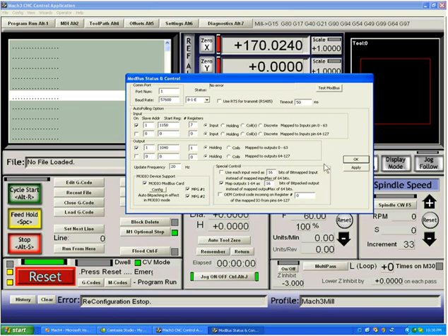Here under Special Control, we have some controls that allow you to configure a bit differently. Normally, each 16-bit word sent to a ModBus control is a 1 or a 0 representing the pin number of the position of the register. In this case, however, you can check a box which says use each input word as 16 bits of bitmapped input.